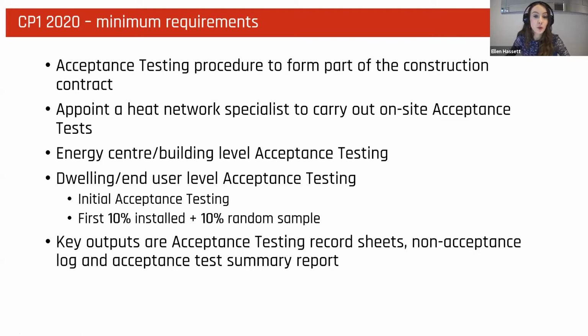So minimum requirements that are outlined in CP1 2020 are as follows. Ensuring the acceptance testing procedure forms part of the construction contract. This is essential as it builds acceptance testing into the development process from day one. Appointing a heat network specialist to carry out on-site acceptance tests. So these acceptance tests are testing the energy centre with a focus on average flow and return temperatures, efficiency, reliability, etc.